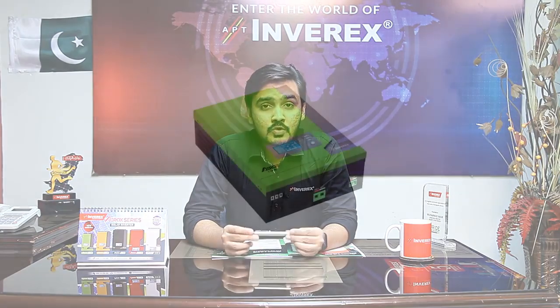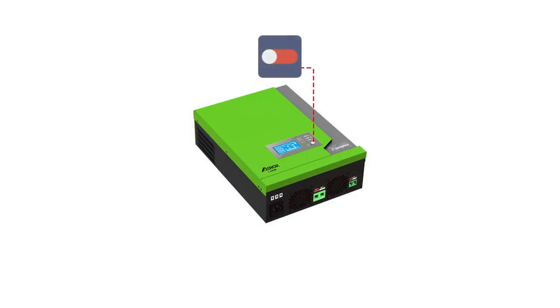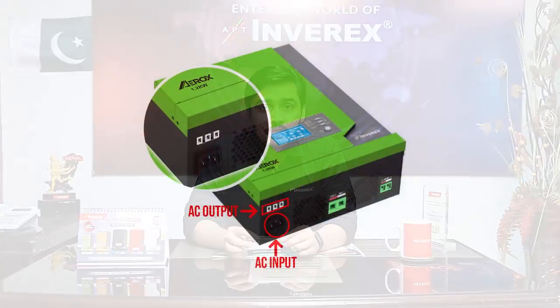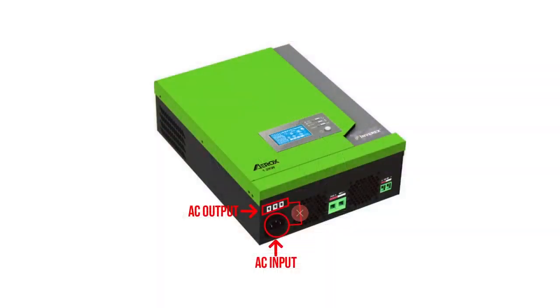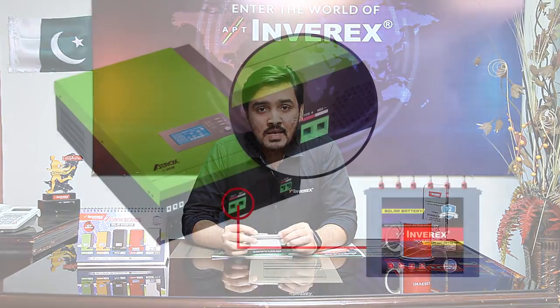When you unpack and install the inverter, attach the AC power cable to the inverter but do not turn it on until all connections are enabled. At the bottom of the inverter on the left side, above the AC input you will also see the AC output. We recommend that for the Inverex Aerox 1.2 kilowatt inverter, the neutral of the input and the neutral of the output should not be common — both site neutrals should be separate so that the inverter remains safe in the event of a surge.